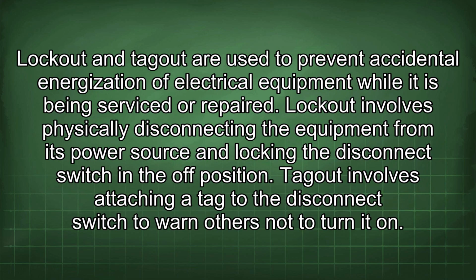Lockout and tagout are used to prevent accidental energization of electrical equipment while it is being serviced or repaired. Lockout involves physically disconnecting the equipment from its power source and locking the disconnect switch in the off position. Tagout involves attaching a tag to the disconnect switch to warn others not to turn it on.